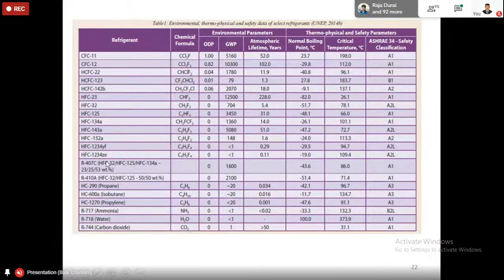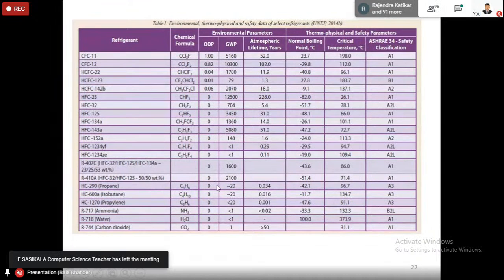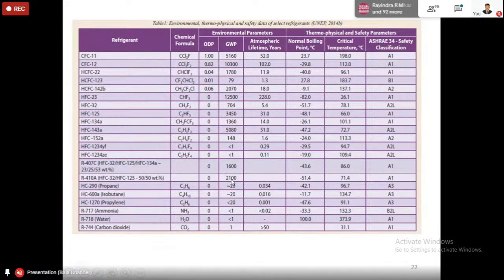This 410A, as you can see, is 32 plus 125. It is a mixture, and it has GWP. Compared to others like 22, which has around 1780, 410A has around 2100 GWP. Still it has GWP, but in India, 410A or 32 is being utilized in air conditioning applications.